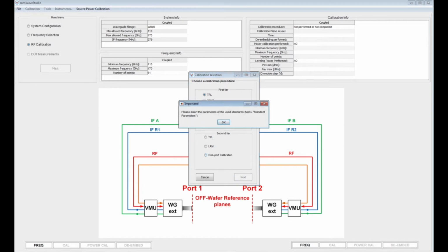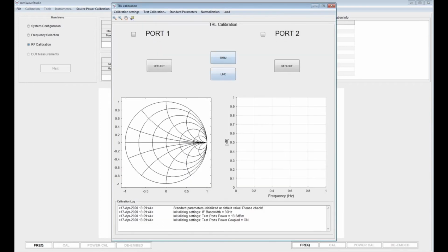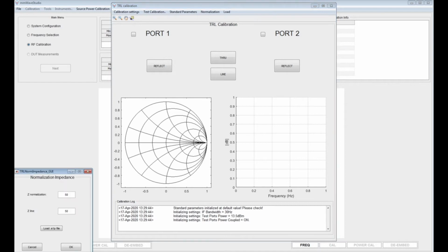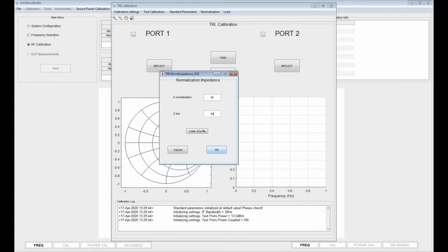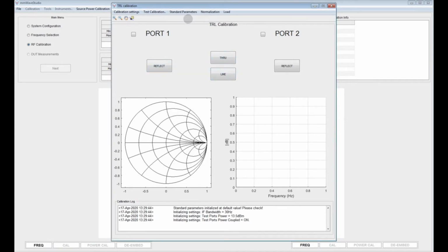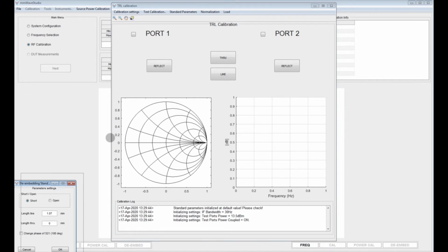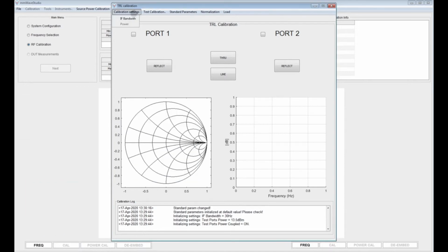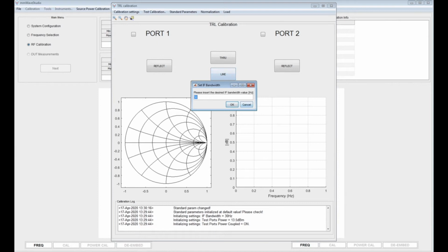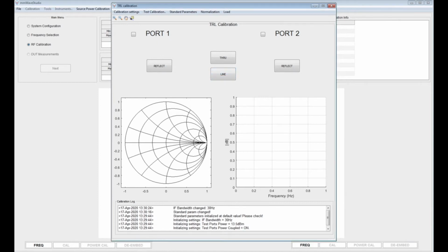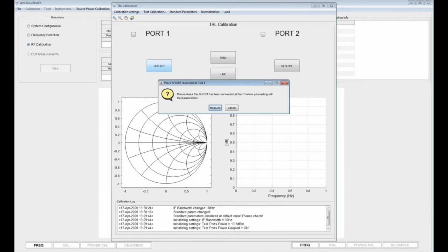In the TRL calibration window, we can load error terms if we have already calibrated the system using WinCal. We can change the normalization impedance if the line impedance of the TRL kit is not 50 ohms or we want to change the system's reference impedance. We can modify the parameters of our calibration standards. And we can specify the IF bandwidth used for the calibration. Now we can measure our calibration standards.